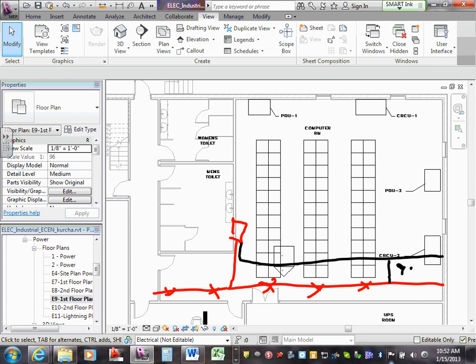The VESDA that you have underneath the floor, for the pre-action system, it's going to be in the ceiling mount. It's going to spray everything, unless they do a clean agent system, but I think it calls out for just a pre-action sprinkler system. Have you guys had a sprinkler contractor in here? No.